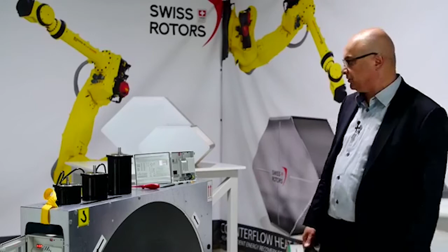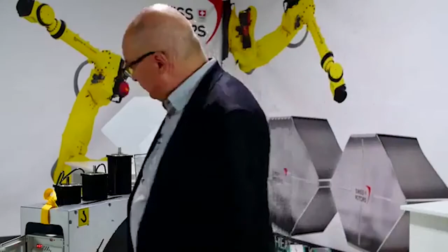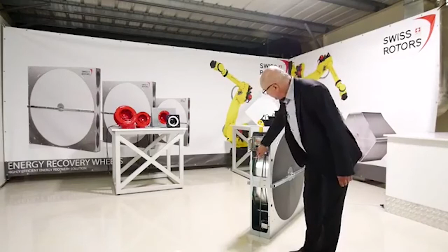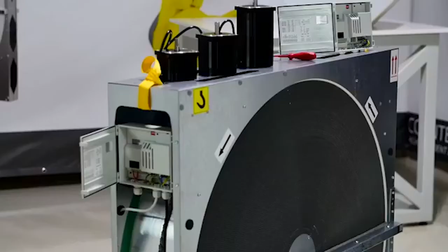But also what is good, it could be used like a normal motor without any controller, just on-off signal and a contactor, of course. If it should work like on-off, we just need to make a jumper here, and then when you apply the power, it starts to rotate. I can show you. I just remove the power, so it will stop. It is stopped now, and then you have a signal to run the wheels. You just put on the contactor and it will start to rotate smoothly, and there is some period when it is accelerating. So very easy, and of course it also has some protection inside, so you don't need to put additional circuit breakers for that.